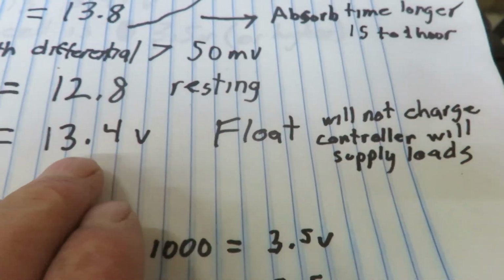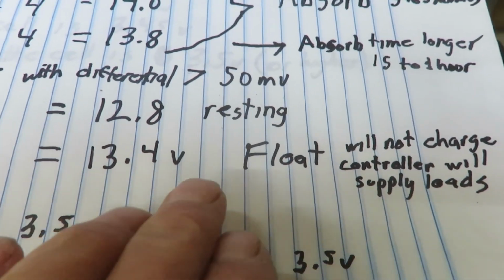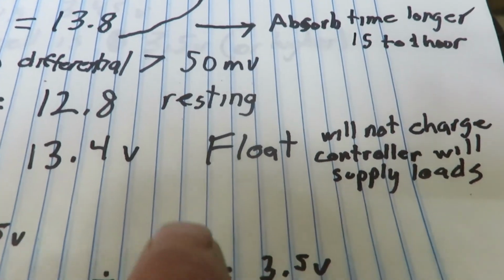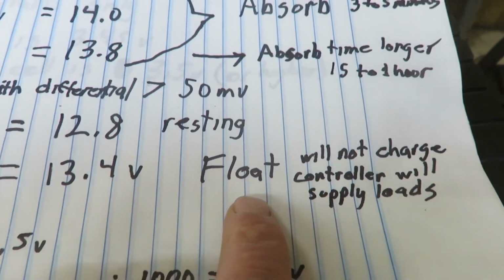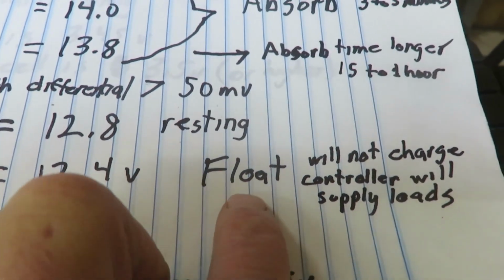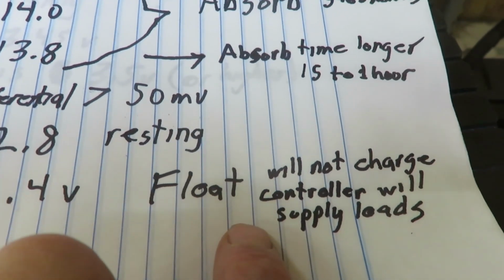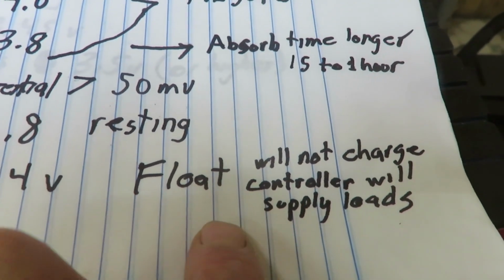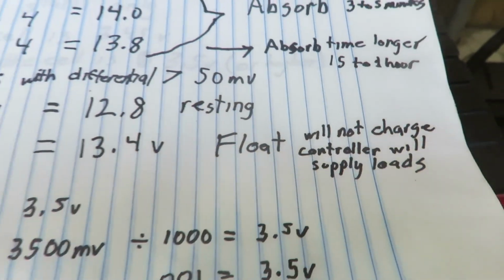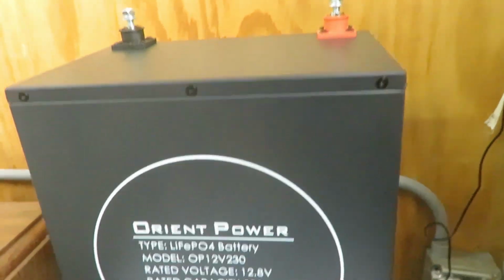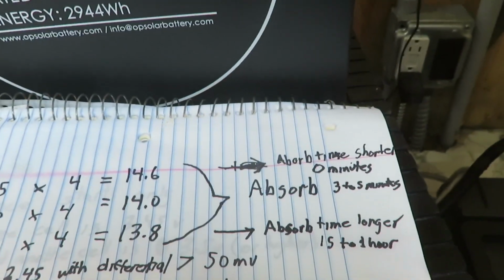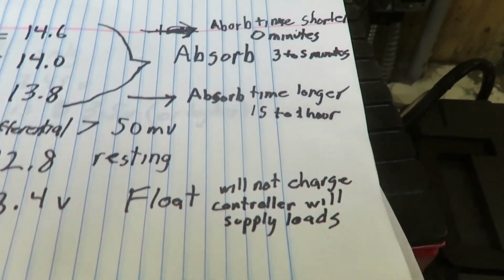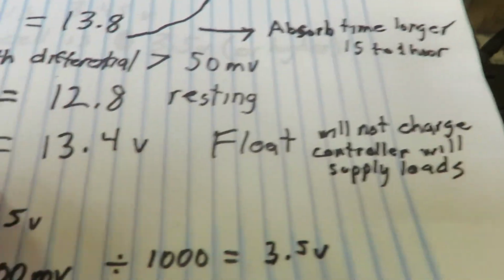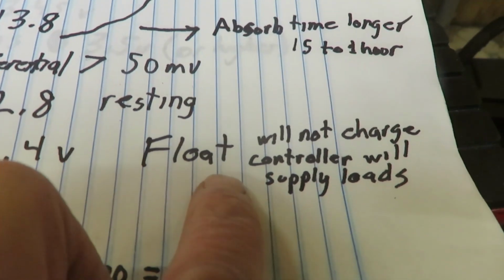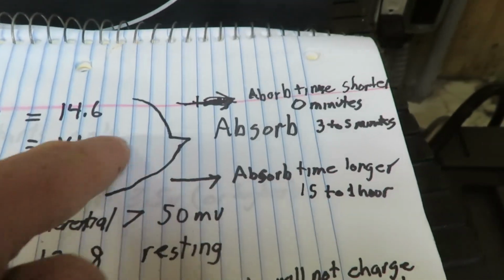So let's say you have a 50 amp load on the battery, and you have 50 amps coming in from the solar panels, and it's floating at this voltage. The controller is going to let it take the 50 amps to the loads, but it's not going to put any more power into the battery cells. With these lithium batteries, you just want to charge them once a day full and then not charge them anymore. This voltage will let them not charge anymore until the next day, then you go through the cycle again.